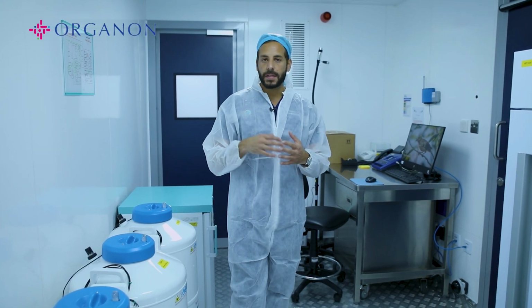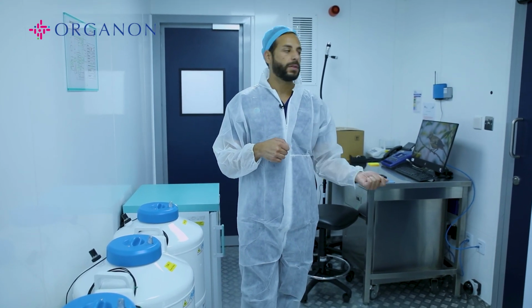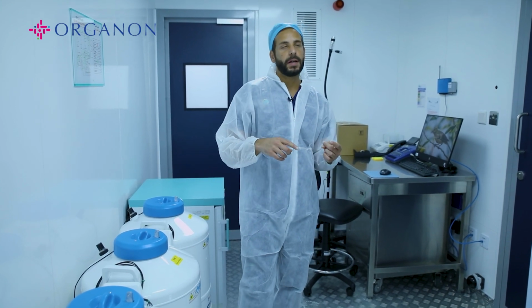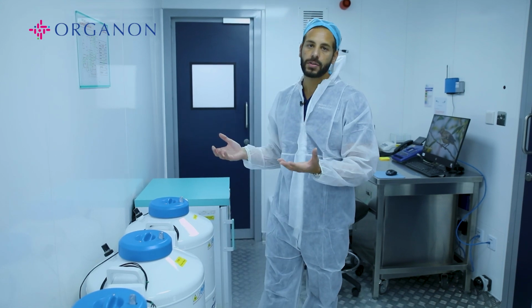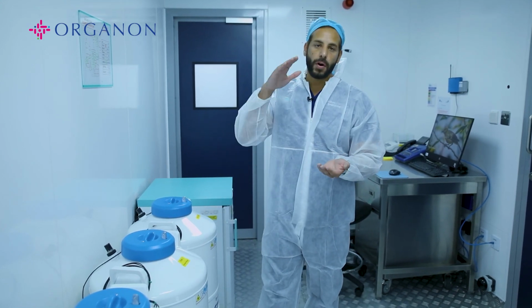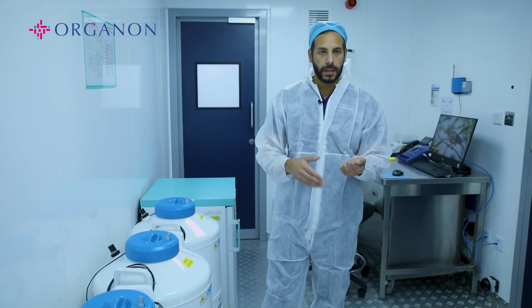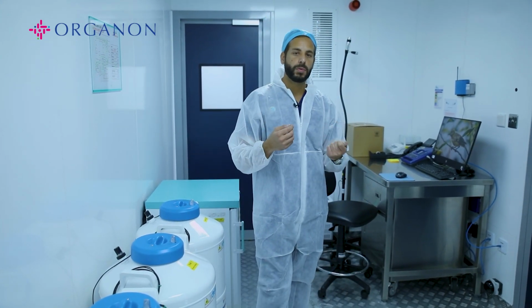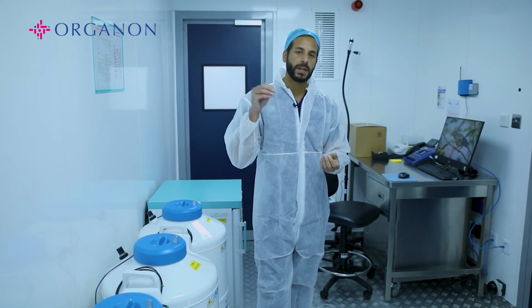So in case there is a leakage or dry out in any of these tanks, the temperature will go up and we will be immediately notified so that we can take direct action. In addition, we have an oxygen sensor in this room, so again, in case there is any leakage in one of the tanks, the oxygen levels will go down. The system will notify us, we will get an alarm inside the lab, and also receive a text message specifying the oxygen levels inside this room.